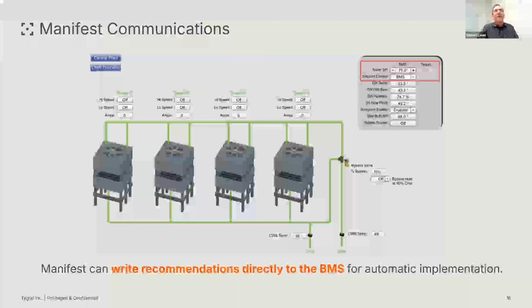That's an example of how it looks in a BMS. In most cases where this has been implemented, the BMS screen has an additional value for our recommendations for all the control set points it affects. The crucial piece is that we deploy the solution on top of the existing BMS. I'll come back to that, but it doesn't require a whole new rollout of the user interfaces already in use.